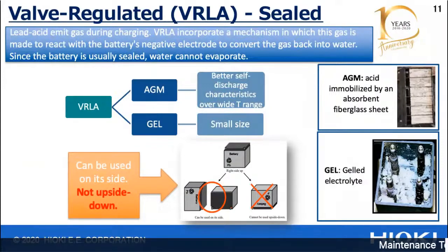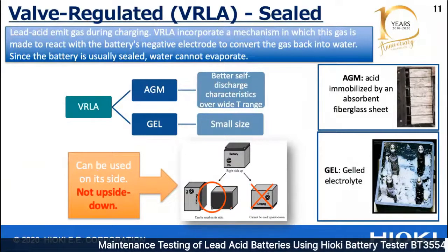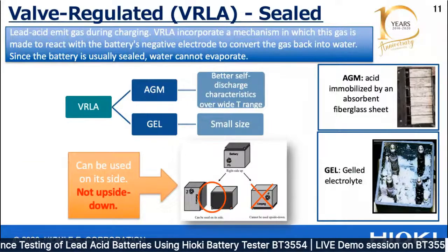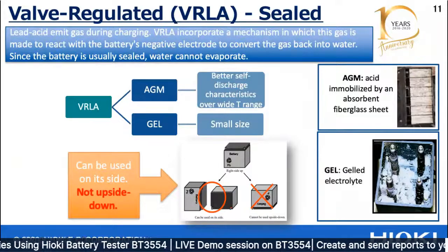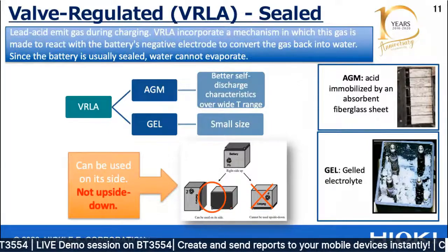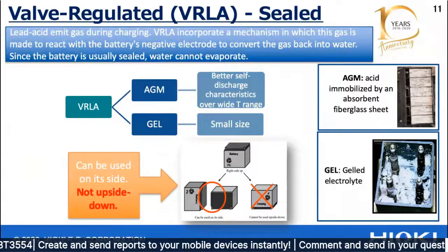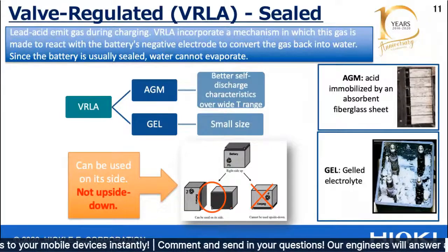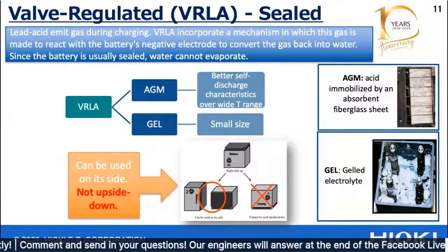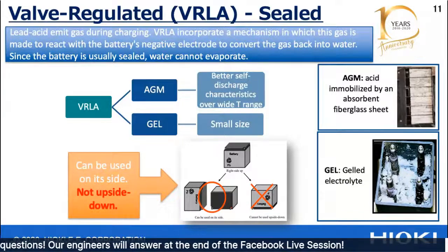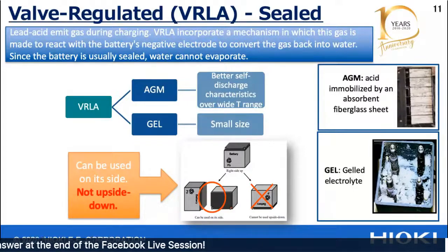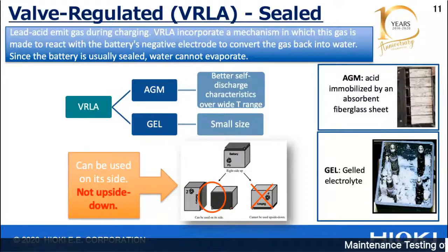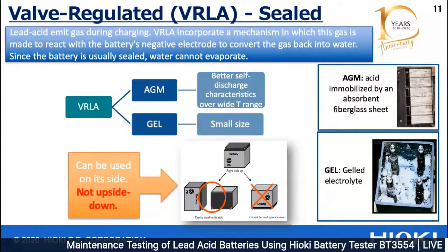Based on the two types, we have the AGM and the gel type. The AGM battery features a fiberglass mesh between the battery plates, which serves to contain the electrolyte and separate the plates, so it has a better self-discharge characteristic over the temperature range. The gel battery uses a jellified electrolyte, where the sulfuric acid is mixed with fumed silica, which makes the mixture gel-like and immobile. The gel battery reduces electrolyte evaporation and spillage, which leads to fewer corrosion problems, which are very common for the wet cell battery. This also gives greater resistance to shocks and vibration.